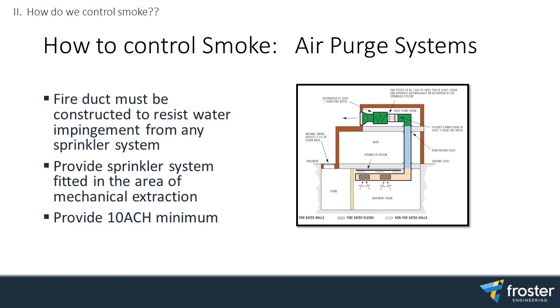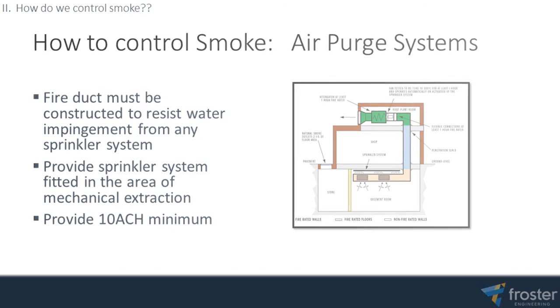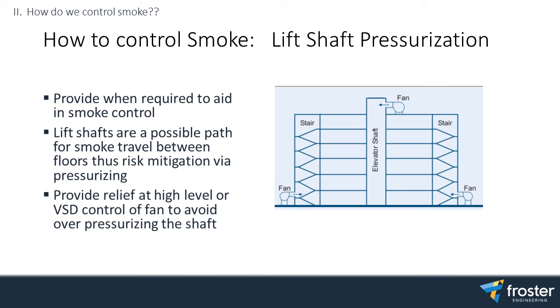Air purge, that's pretty basic. Get a zone extracted, purge there. Lift shaft pressurization, very similar to stair pressurization. To be sure, be mindful that we provide relief at high level, architectural relief louvers. Given the piston effect of the lift, we want to make sure that smoke can get out at high level.